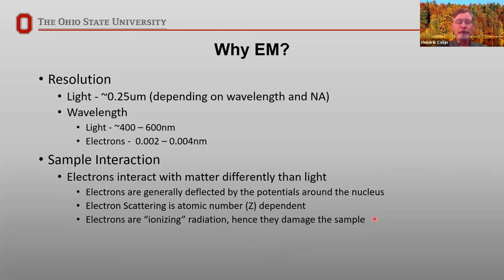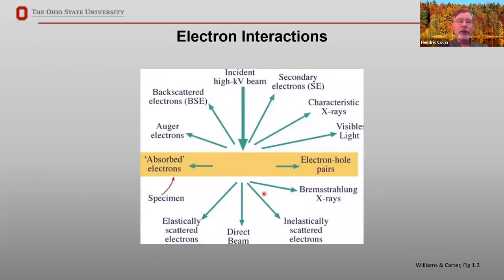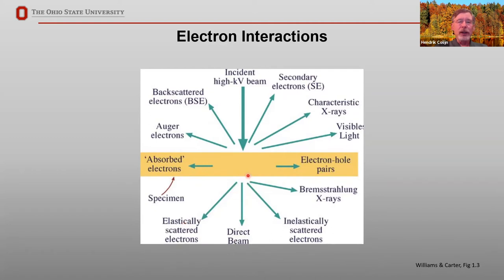As electrons strike the sample, a number of things can happen. Your beam can generate secondary electrons, backscattered electrons, and characteristic X-rays — all of which you look at in the SEM. You can also get visible light generating cathodoluminescence, and Auger electrons for surface analysis. For TEM, we're primarily interested in what is transmitted through the sample: elastically scattered electrons for imaging, inelastically scattered electrons for EELS analysis, and characteristic X-rays for EDX analysis — similar to the SEM but at higher spatial resolution.